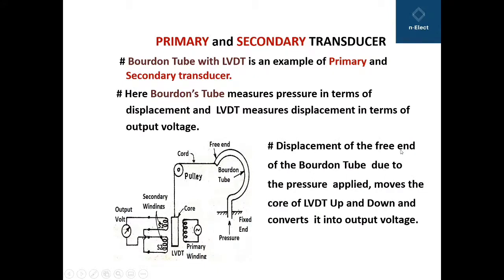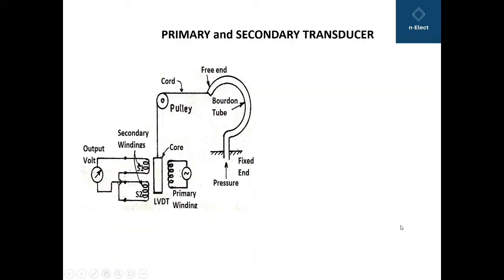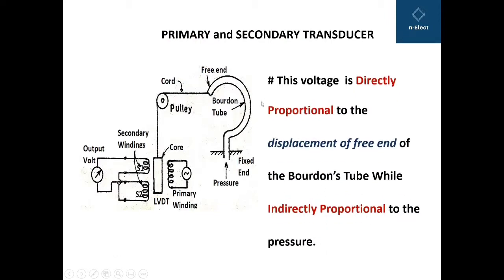Displacement of the free end of the Bourdon tube due to the applied pressure moves the core of the LVDT up and down and converts it into an output voltage. Thus, the output voltage is proportional to the displacement of the free end of the Bourdon tube, while this is indirectly proportional to the pressure. It means pressure is being converted into displacement of the free end, and that displacement is being converted through the core into the output voltage.